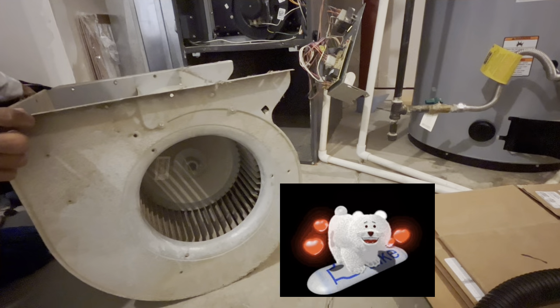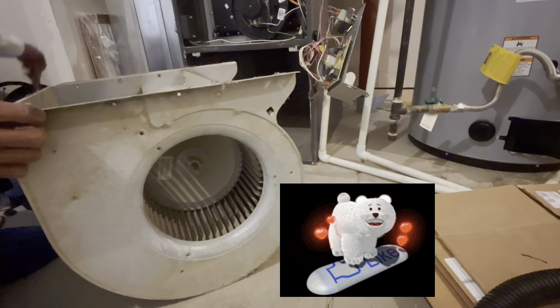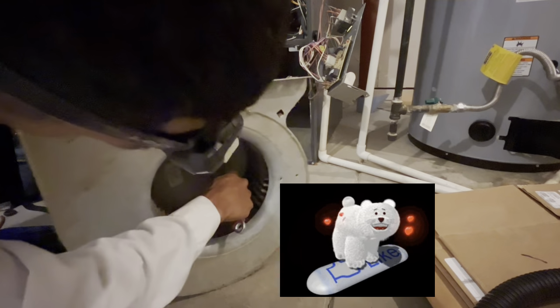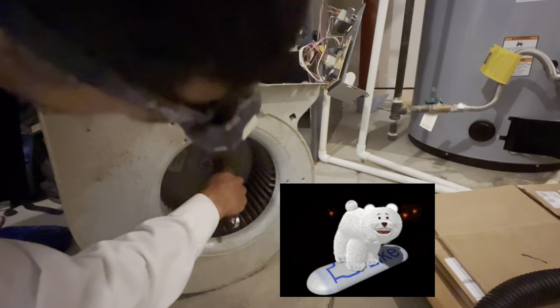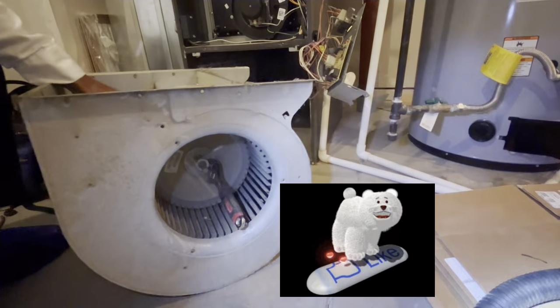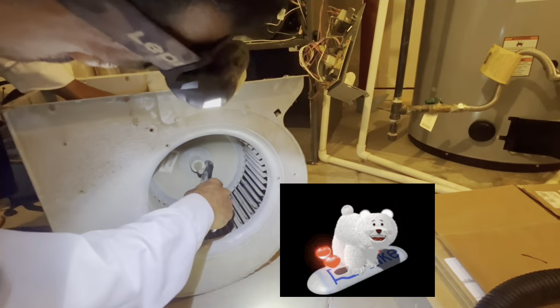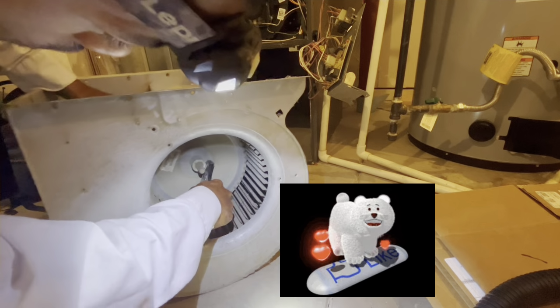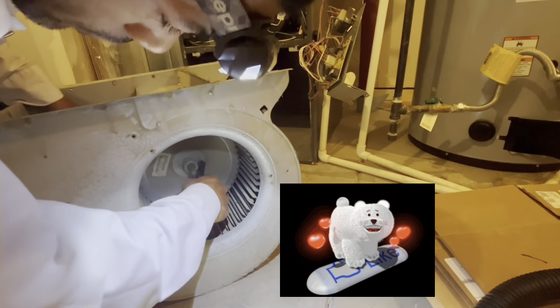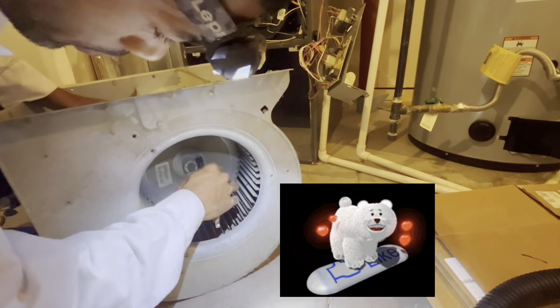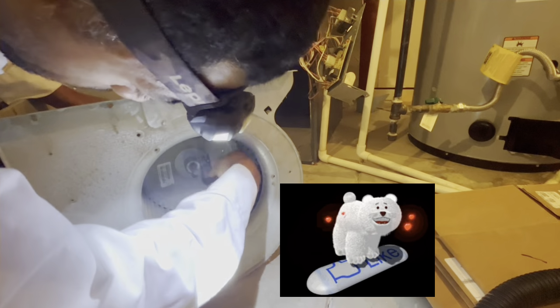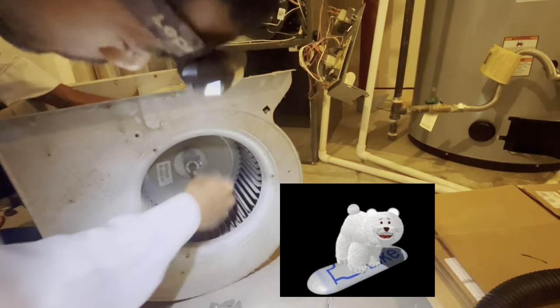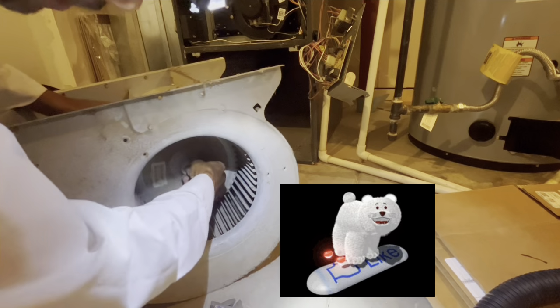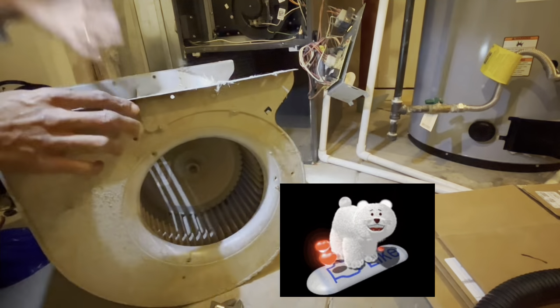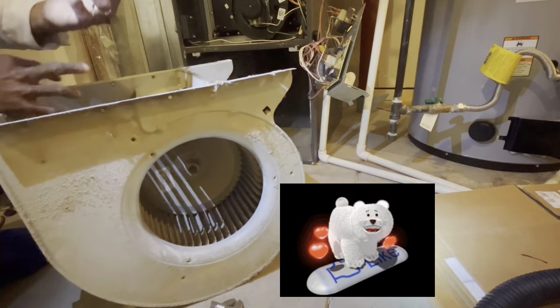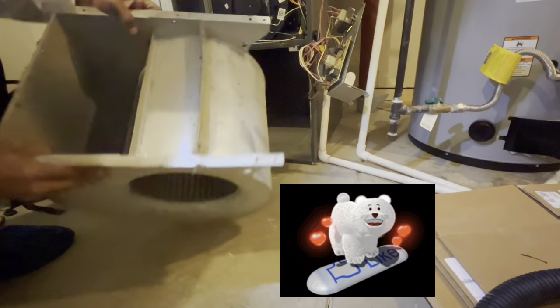So now I'm going to get my crescent wrench and break that set screw loose that holds the motor shaft to the blower wheel. I always put it a certain way and hit it with my hand to break it loose, because I've had my hand in there, just turned it, and hit my hand on the wheel, and then you're bleeding, or your hand is hurting from hitting metal. So, try not to do that.